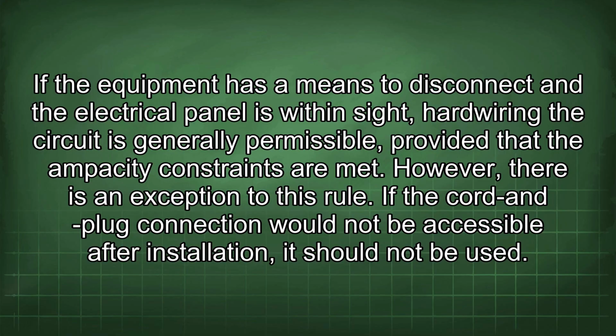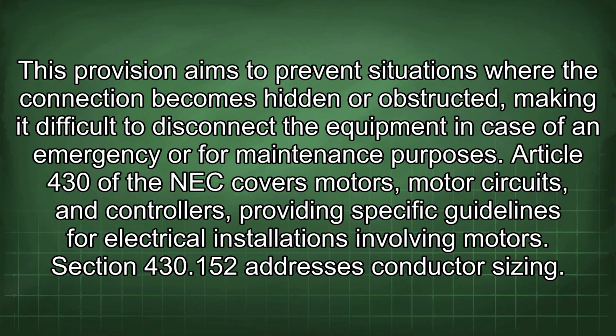If the cord and plug connection would not be accessible after installation, it should not be used. This provision aims to prevent situations where the connection becomes hidden or obstructed, making it difficult to disconnect the equipment in case of an emergency or for maintenance purposes. Article 430 of the NEC covers motors, motor circuits, and controllers, providing specific guidelines for electrical installations involving motors.